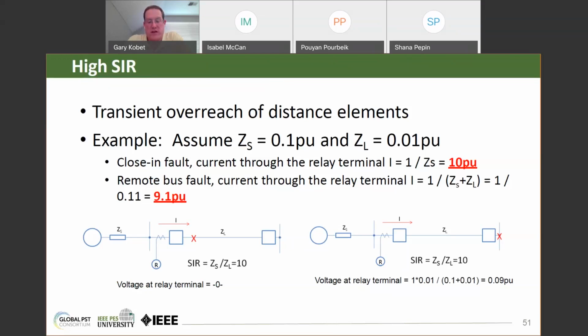So this is another issue, and so for cases where you have high source impedance ratio, there are times where zone 1, an instantaneous underreaching element, cannot be set, and even pulling zone 1 back may not be enough. You may have to pull zone 1 back to the point where it's almost useless.